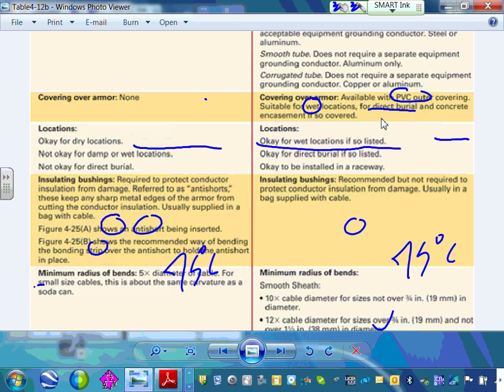Concrete encasement. Now, can I bury this one in concrete? No. Can I buy an MC cable that has a PVC cover that can be buried in concrete or in the dirt? Yes. But typically, guys, we don't do that one. For most applications, if you go underground, it's PVC.